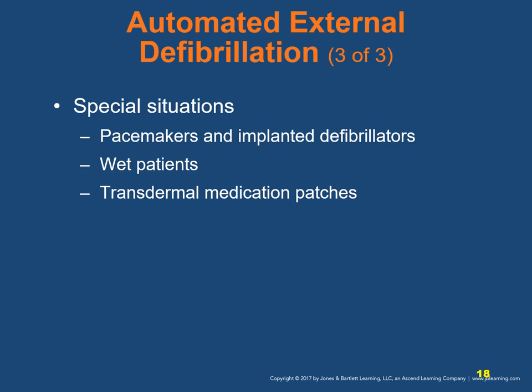Wet patients. Do not use the AED unit in water. If the patient is in water, pull the patient out and dry the skin before attaching the AED pads. If the patient is in a small puddle of water or in the snow, the AED can be used, but the patient's chest should be dried as much as possible.